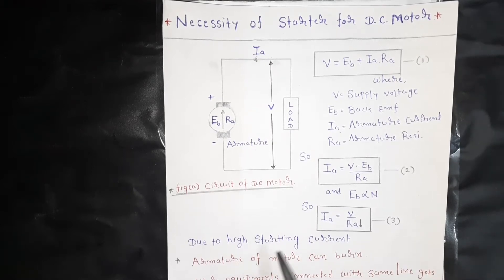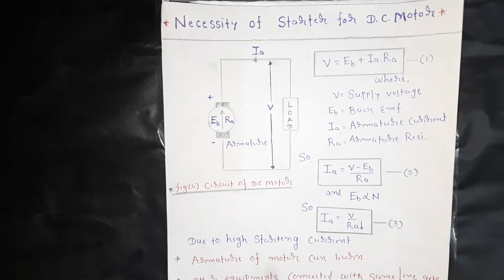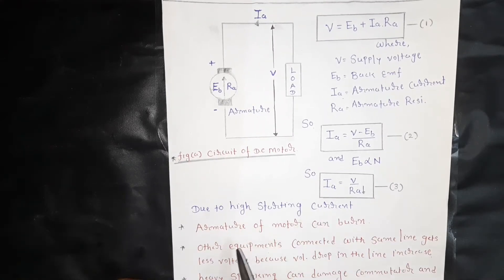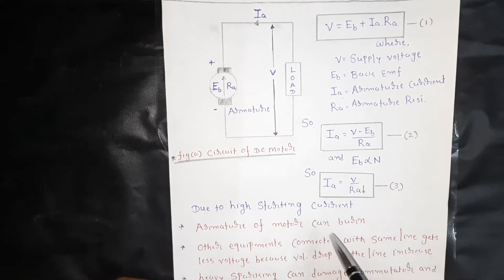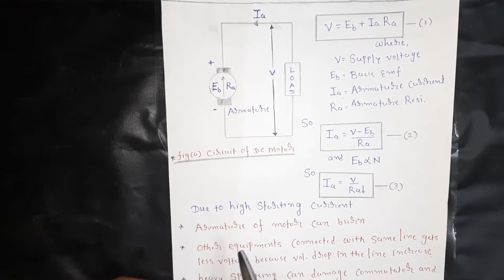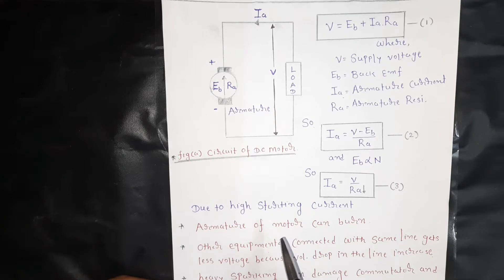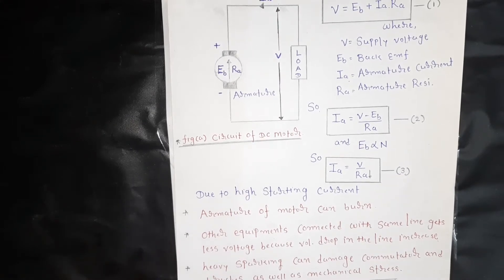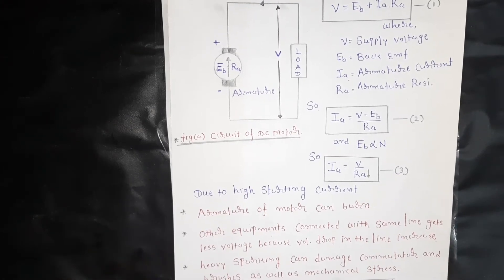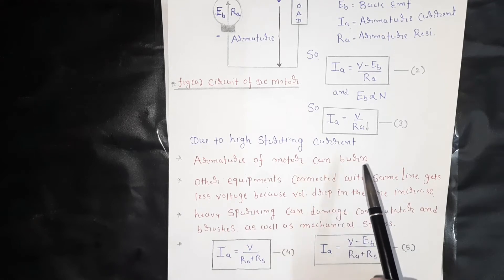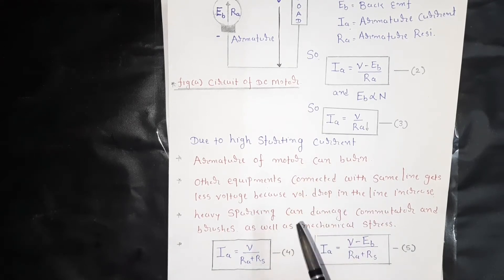Due to the higher starting current, there are many problems created in the DC motor. Due to the higher starting current, the armature of the motor can burn. The voltage drop in the line also increases, and if some equipment is connected to the same line, other equipment will get lesser voltage. Heavy sparking can damage the commutator as well as the brushes, and it will also create mechanical stress to the DC motor.